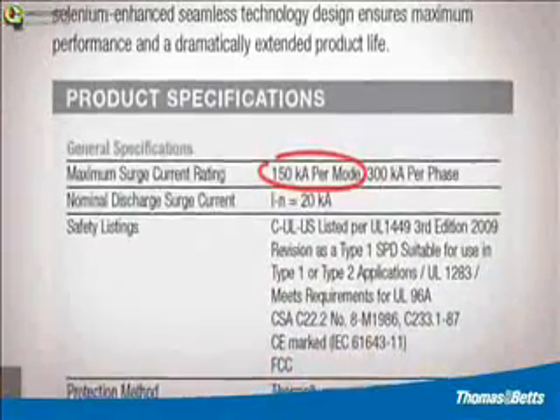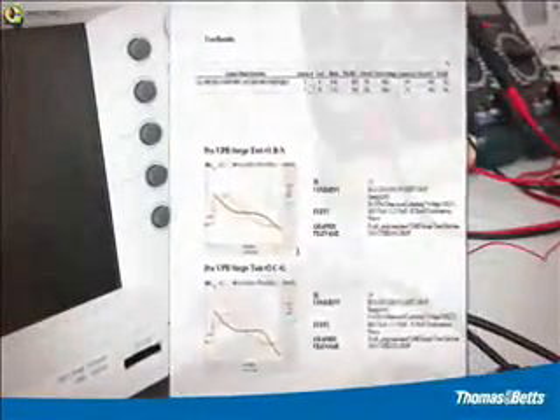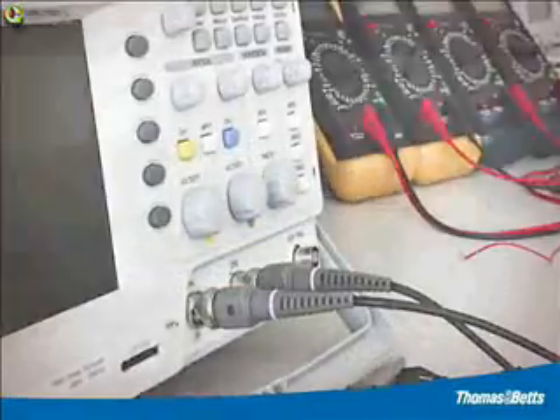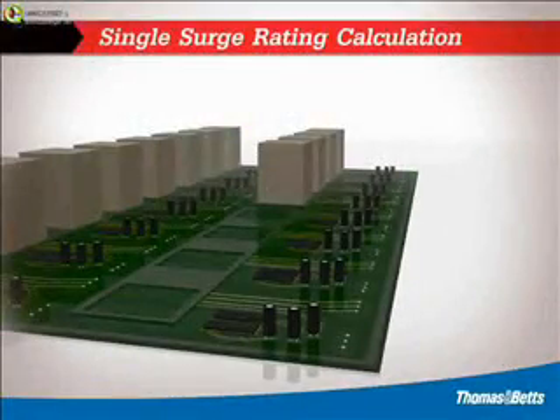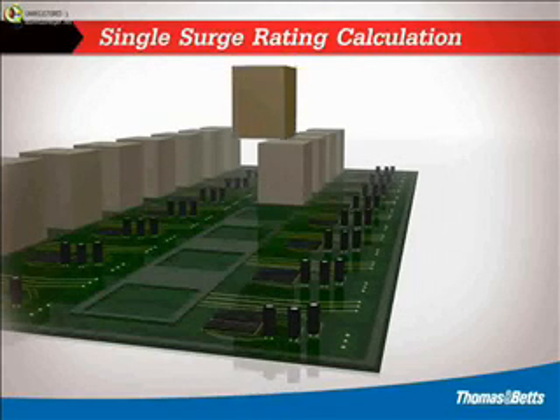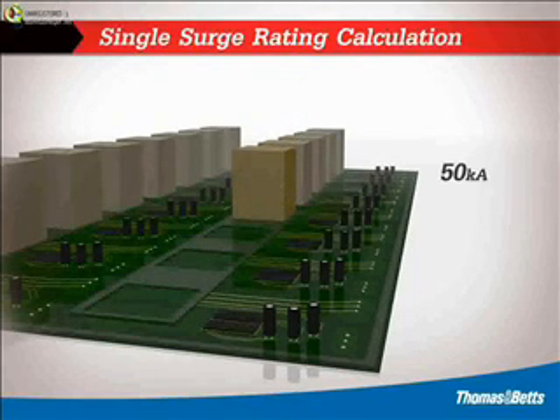devices. Every surge protective device is marketed based on its single surge handling capability, the level of surge the unit is capable of handling one time without failure. Historically, surge manufacturers provided third-party test reports to prove their product's robustness. Presently, most surge manufacturers do not provide test reports. Instead, they provide calculated values based on the number of surge components used in the construction of their product.